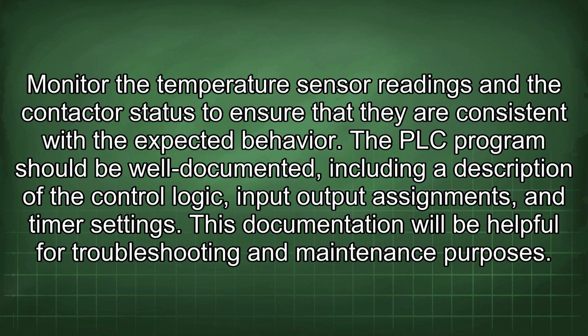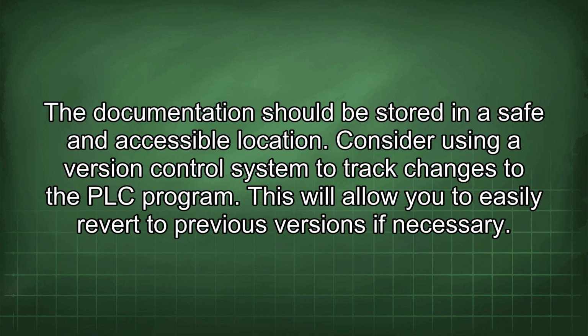The PLC program should be well documented, including a description of the control logic, input-output assignments, and timer settings. This documentation will be helpful for troubleshooting and maintenance purposes. The documentation should be stored in a safe and accessible location. Consider using a version control system to track changes to the PLC program. This will allow you to easily revert to previous versions if necessary.